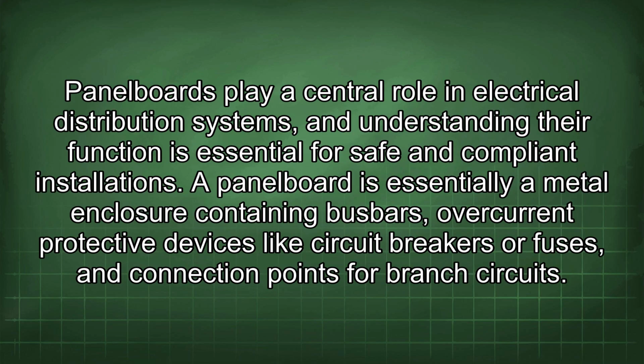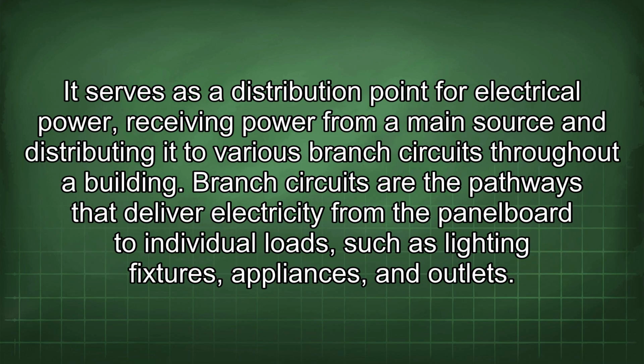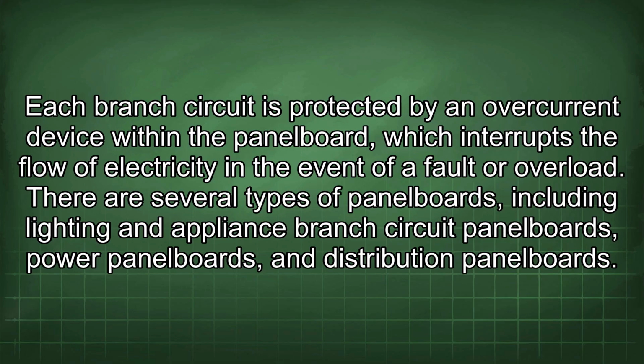Panel boards play a central role in electrical distribution systems, and understanding their function is essential for safe and compliant installations. A panel board is essentially a metal enclosure containing busbars, overcurrent protective devices like circuit breakers or fuses, and connection points for branch circuits. It serves as a distribution point for electrical power, receiving power from a main source and distributing it to various branch circuits throughout a building. Branch circuits are the pathways that deliver electricity from the panel board to individual loads, such as lighting fixtures, appliances, and outlets. Each branch circuit is protected by an overcurrent device within the panel board, which interrupts the flow of electricity in the event of a fault or overload.